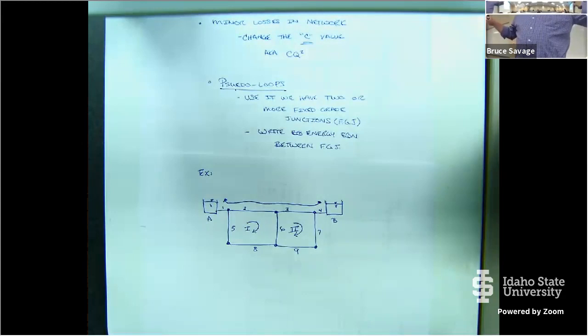And that's a good thing because that's how I bring the flow rate from those 2 pipelines into my equation. They're built into the continuity equations at those 2 nodes, but they're not built into the energy equation. So the pseudo loop brings the connecting pipes from my 2 fixed grade nodes into my set of equations, and then will help me solve those 2 flows.